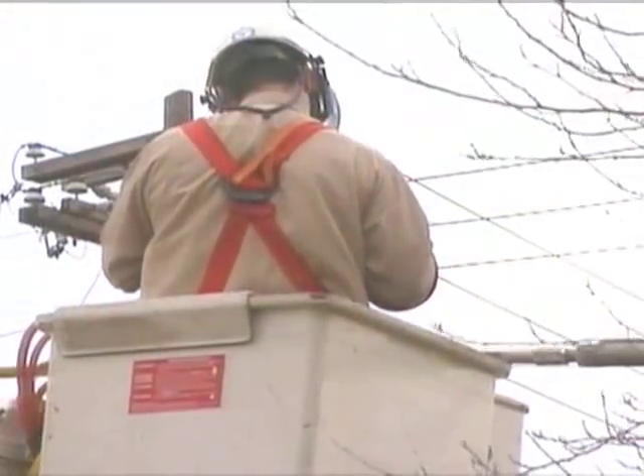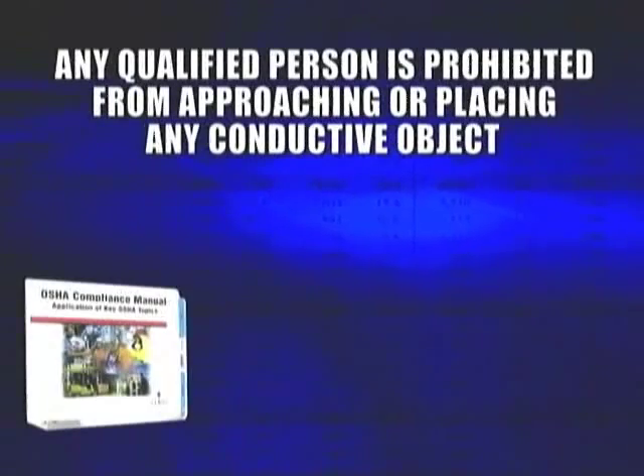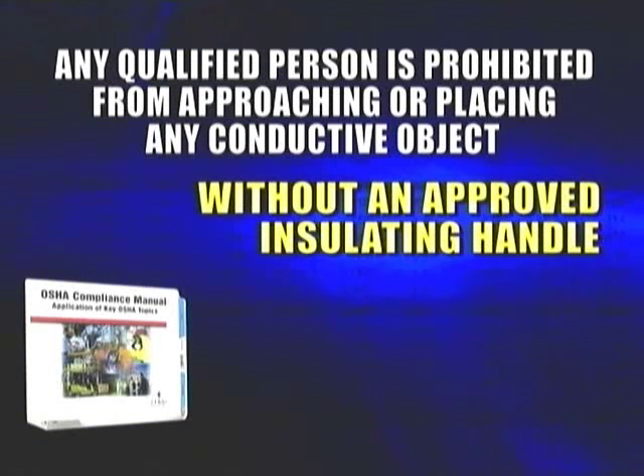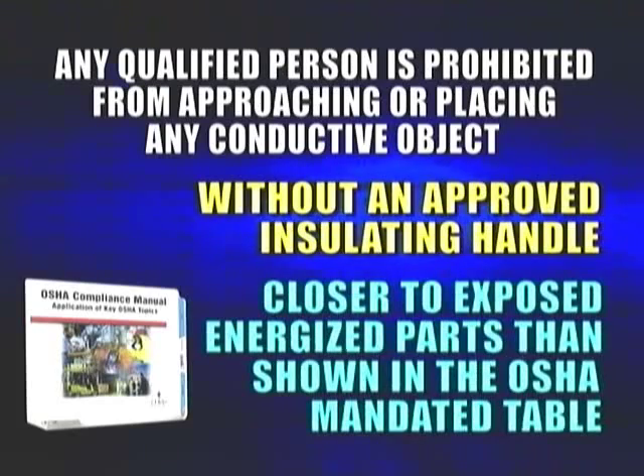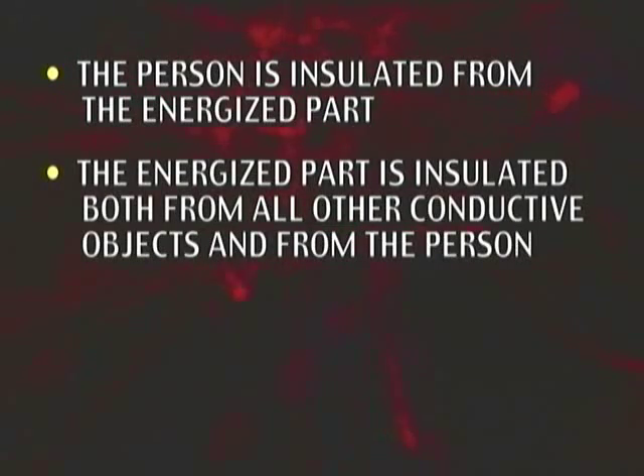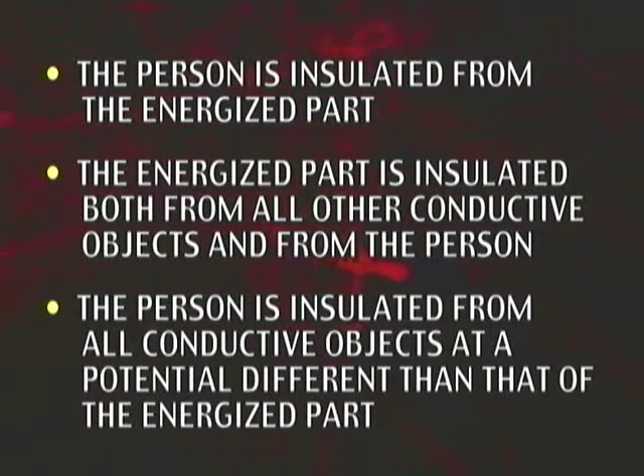When a qualified person is working in the vicinity of energized lines, whether in an elevated position or on the ground, they are prohibited from approaching or placing any conductive object without an approved insulating handle closer to exposed energized parts than shown in the OSHA-mandated table, unless the person is insulated from the energized part, the energized part is insulated both from all other conductive objects and from the person, and the person is insulated from all conductive objects at a potential different than that of the energized part.